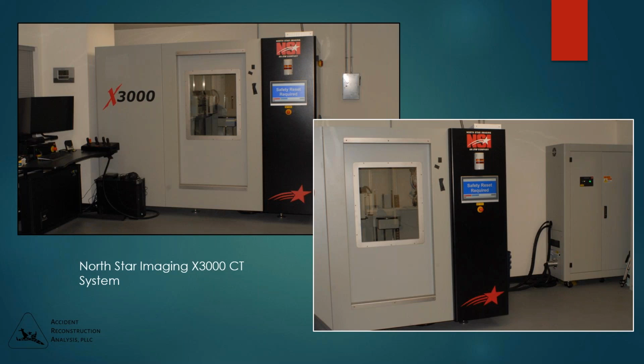Again, this instrument is not small. You can see the imaging console at the center of the top left photograph, the computer to the left of that, and at the bottom right the sample chamber, and then the console to the right, which is the power and cooling supply for the X-ray tube. The high voltage generator and other components are contained within that cabinet. All of the components for obtaining the imagery are within the main cabinet.